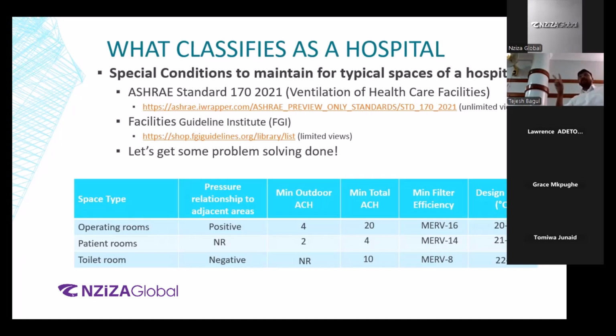The second point is regarding maintaining a laminar flow in your operating rooms. Going back to our studies, there are three types of flows: laminar, transient, and turbulent, based on the Reynolds number. The operating room typically has one central patient bed. It will have big booms, surgical booms they call them, on the top. The doctors and the nurses will be around the table doing the surgery, right? So in that case, you need to make sure that the air coming from that surgical boom is properly laminar. It does not mix again and again. We don't want that happening. Mixing just gives the contaminants an option to go into the surgical area, right? And that is how you will create a laminar flow.